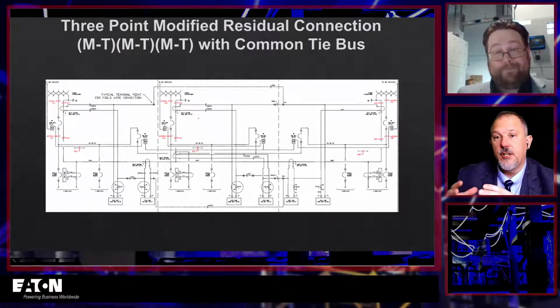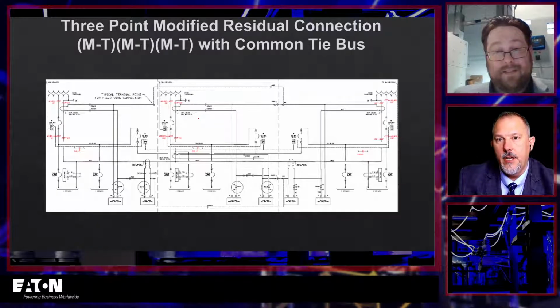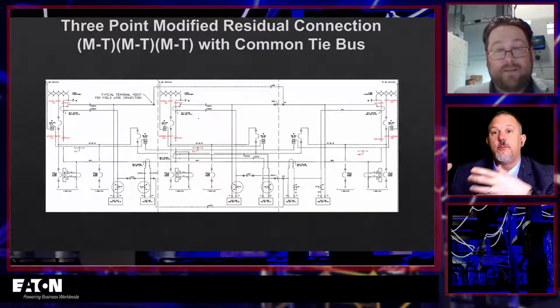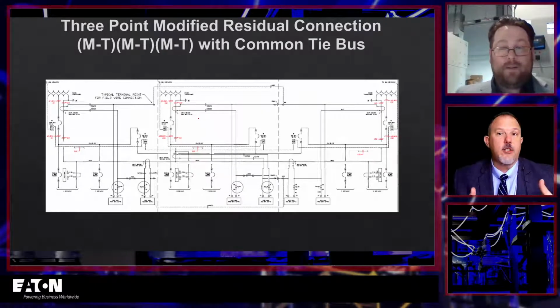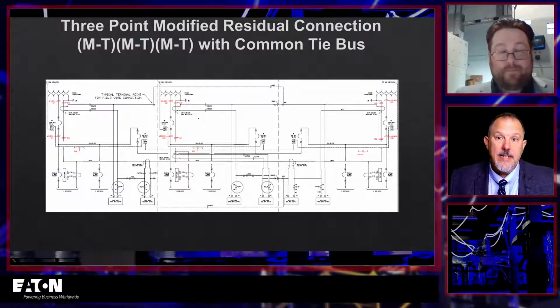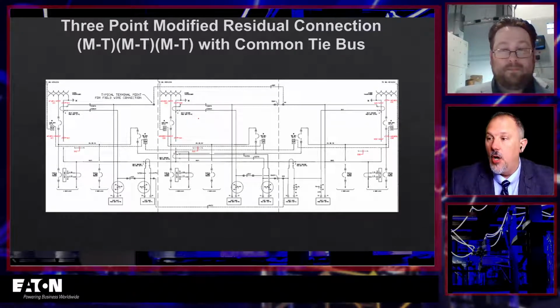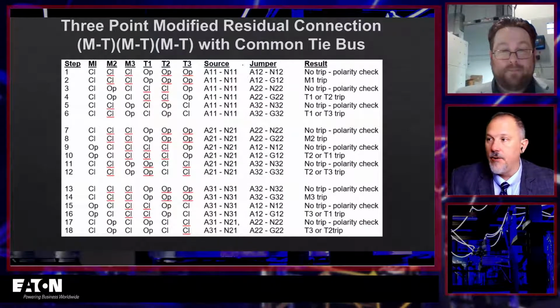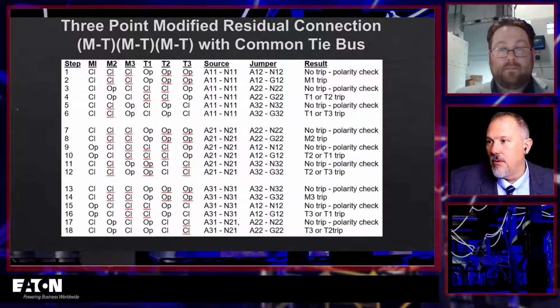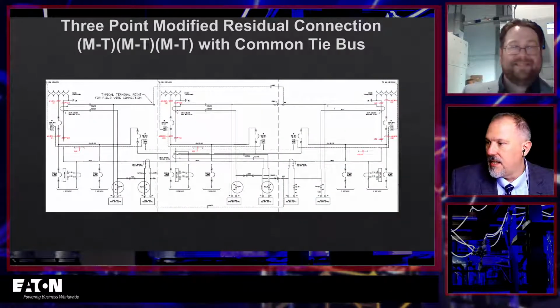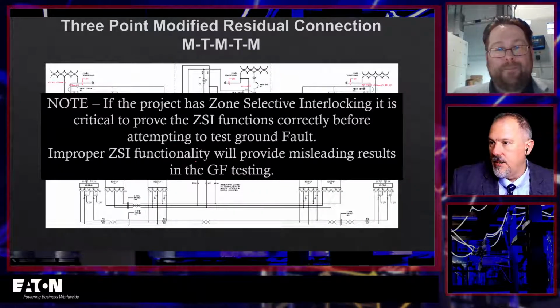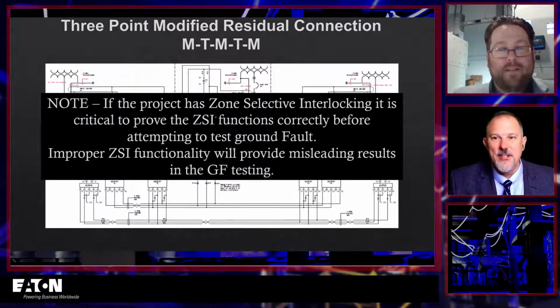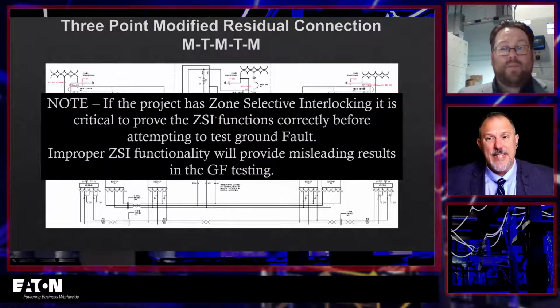Yeah, because like you say, you take a lineup like this, which is very complicated, and you don't want the customers terminating all of their feeds, because you're going to have to disconnect all of that anyway. You're being surgical about it to figure out all of these test points, every source, where your jumpers are going to be, and what the test results need to be. So you're going to have 18 tests on this main-tie. But then on this one here, you've got 3, and if you've got zone selective interlocking and all this other good stuff, you've got to think about that too, because there are jumpers associated with ZSI.